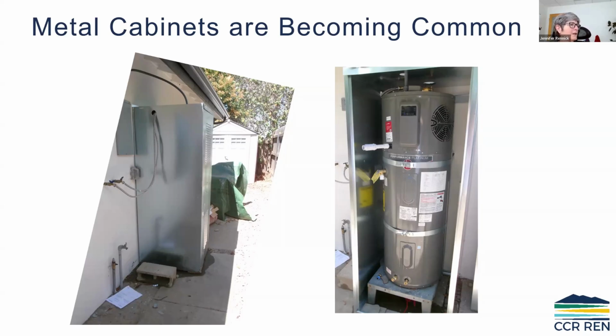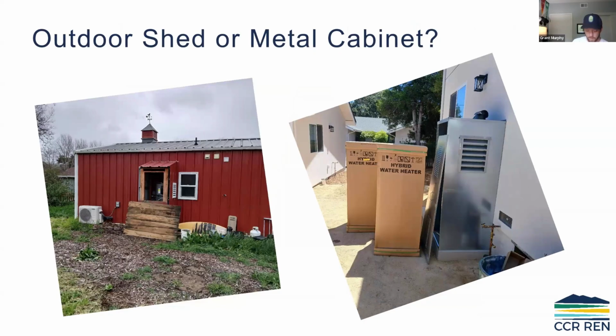If you go back one slide - the slide on the right still has the upper and lower louvers on the door, and the whole cabinet's pretty leaky. But in this case, they actually got one with the louver on the right-hand side, and the tank is angled so that it exhausts right at the louver, which is how the manual recommends you do it. Same with that funky little closet on the left-hand side. So again, if your Title 24 report just says 'outdoors, outdoors, outdoors,' maybe it works if they do everything else, but I don't know.